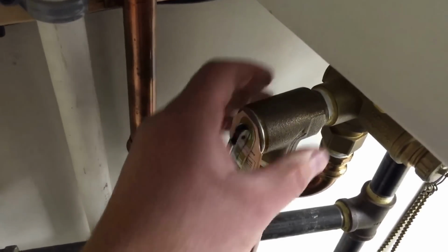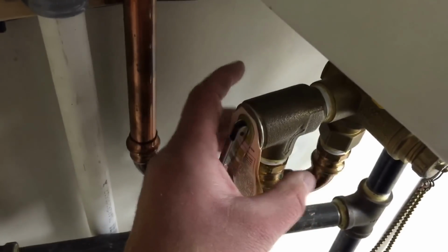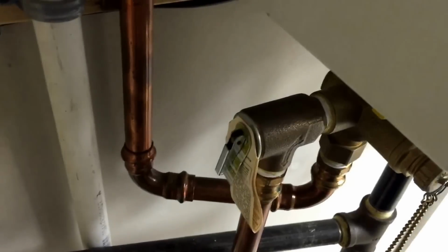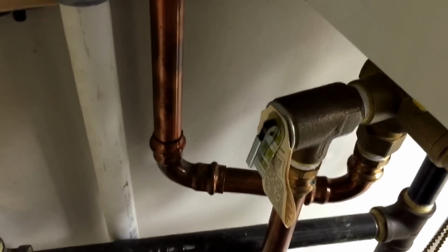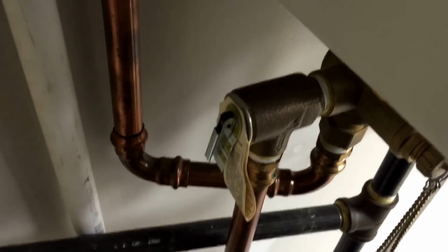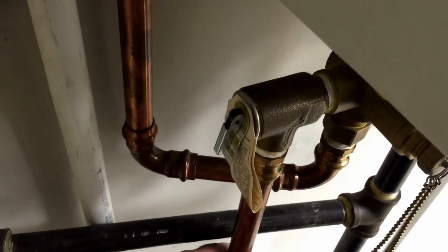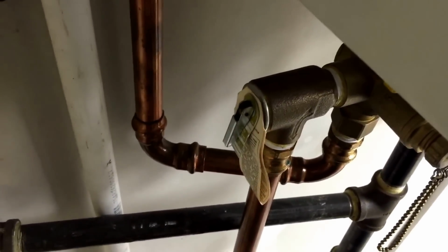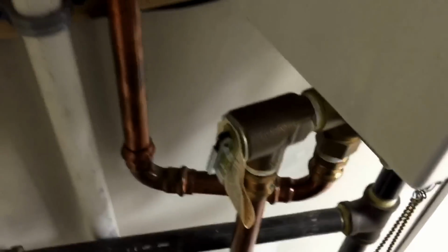Well, that water is scalding hot. So if this valve releases and there's no pipe here, it's just going to spray all over the place. Now, if somebody's standing by that tank, they're going to get burned. That's why you have a pipe. And this is required by code. You just don't put that in there just because you feel like it. The national code requires that.